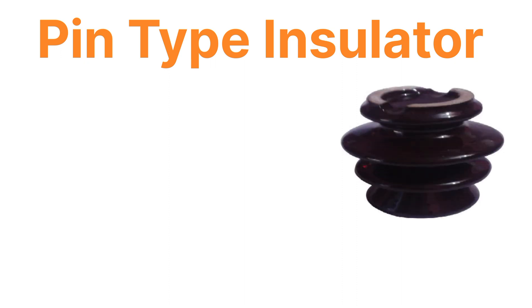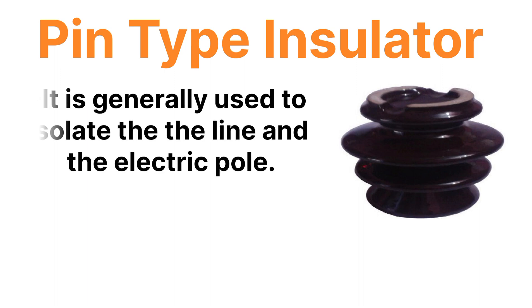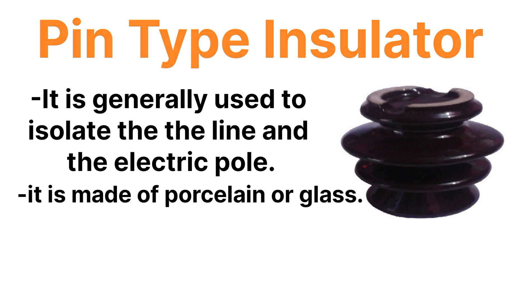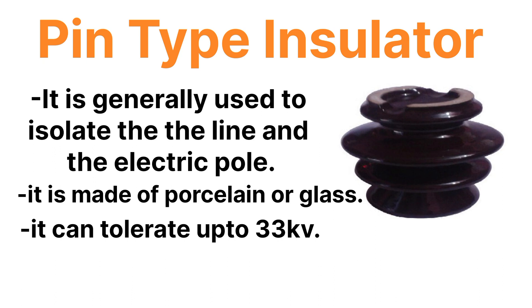The most commonly used insulator in the overhead line is known as the pin type insulator. A pin type insulator is generally used to isolate a wire from the pole, so that current does not flow through the pole. It is made up of porcelain or glass, and it can tolerate up to a voltage of 33 kV.